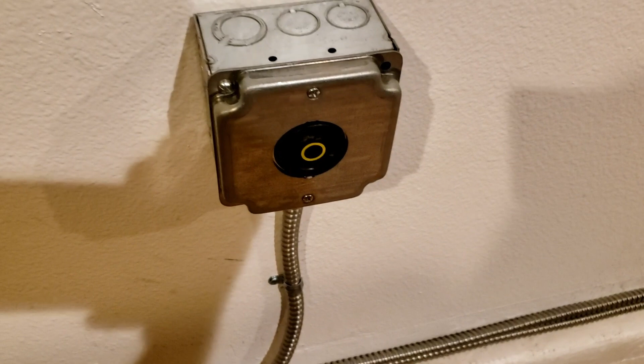I also corrected this outlet because it was wired for 240 volts and needs to be 120 volts. I changed that, rewired it correctly, and wrote a note on a post-it and put it in the box so that later on, if I open this up, it reminds me that the red wire in there has a nut on it, like this guy here, like this guy - there's a nut on the box and one here in the sub panel, because we're not using that wire. But in the future, should I want to change it to a 240 volt outlet, all I have to do is change the receptacle and the circuit breaker. The red wire already runs all the way through, so I've got a red and a black right here, and that can be altered if I need to do that.